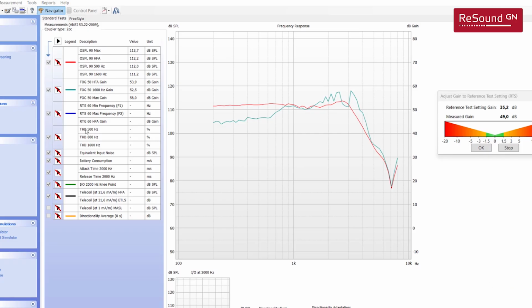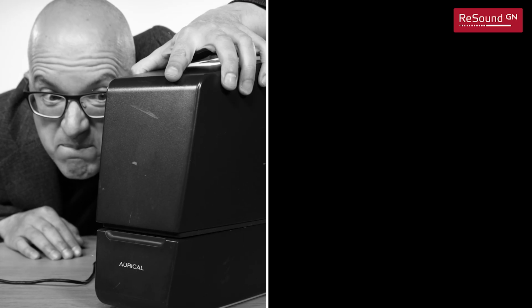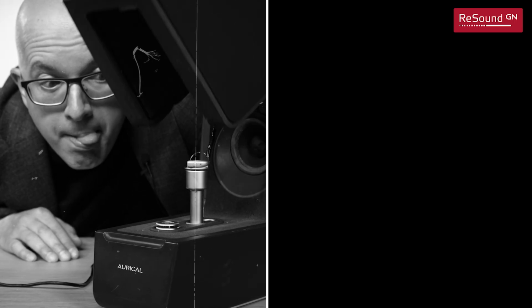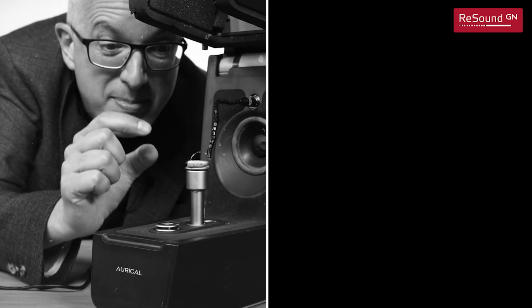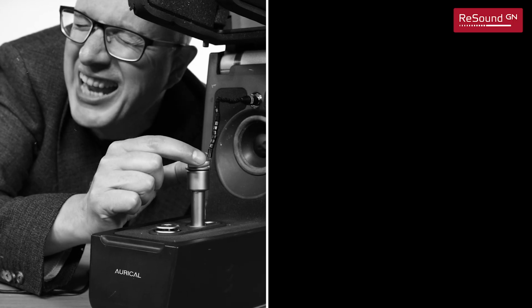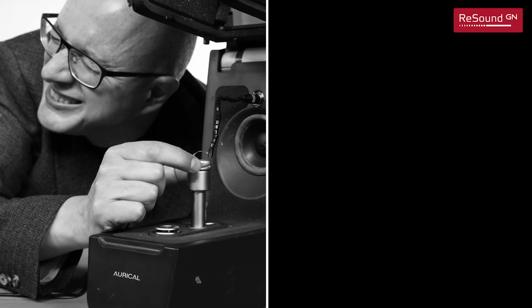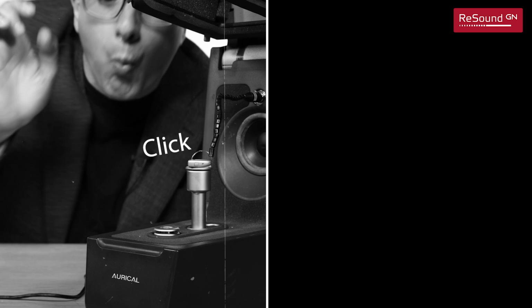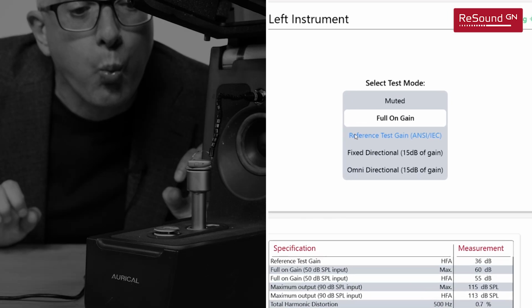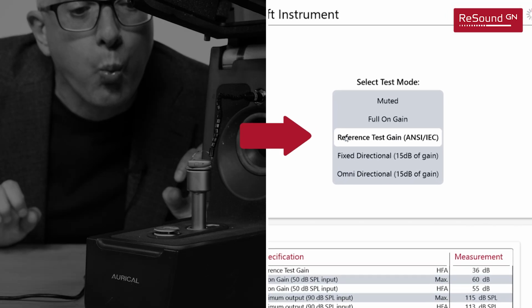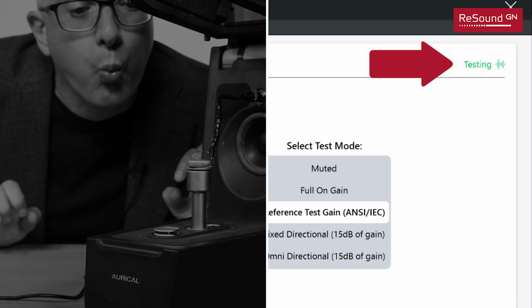Now the test box is asking me to get ready for the second test, which is the reference test gain. Before, to do that, I had to manually change the program of the hearing aid to program 2. Very carefully, not to move the hearing aid during the measurement and never really knowing whether you are in the right program or not. Now I can just select the reference test gain directly from the screen, and with this icon you can easily check the status of your hearing aids during the test. Ready?